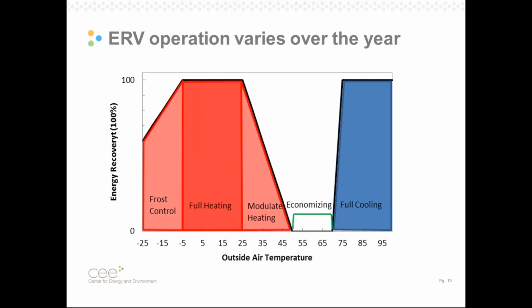In fact, energy recovery is usually so effective that we have to modulate it down so it doesn't overheat the incoming ventilation air. And so that's why this curve increases as we go from 45 or 50 degrees. We have a very low amount of energy recovery to a high amount of energy recovery at around 25 degrees. And so as it gets colder and colder, the energy recovery system works harder and harder, and at some point, say 25 degrees, it can no longer handle the ventilation heating load by itself.